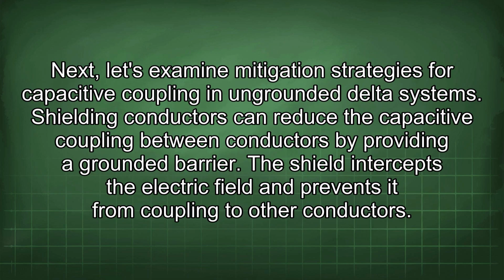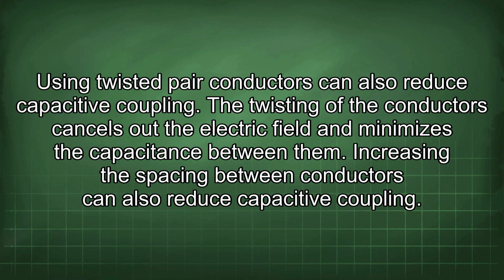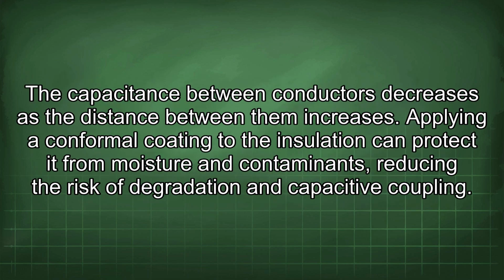Next, let's examine mitigation strategies for capacitive coupling in ungrounded delta systems. Shielding conductors can reduce the capacitive coupling between conductors by providing a grounded barrier. The shield intercepts the electric field and prevents it from coupling to other conductors. Using twisted pair conductors can also reduce capacitive coupling. The twisting of the conductors cancels out the electric field and minimizes the capacitance between them. Increasing the spacing between conductors can also reduce capacitive coupling. The capacitance between conductors decreases as the distance between them increases.